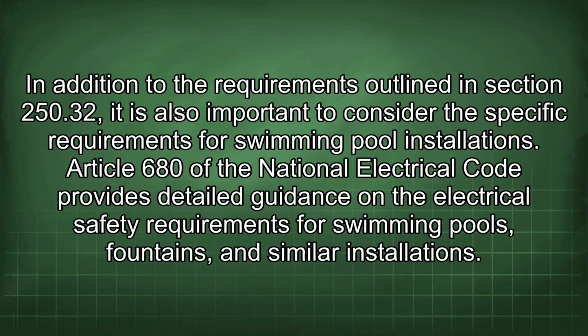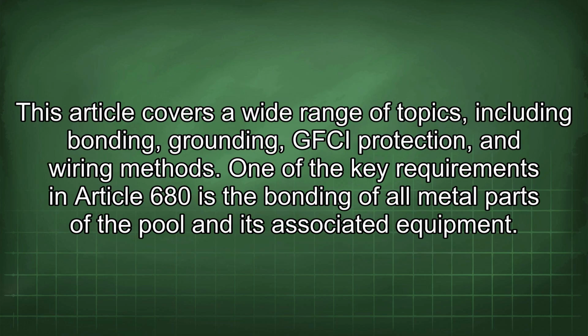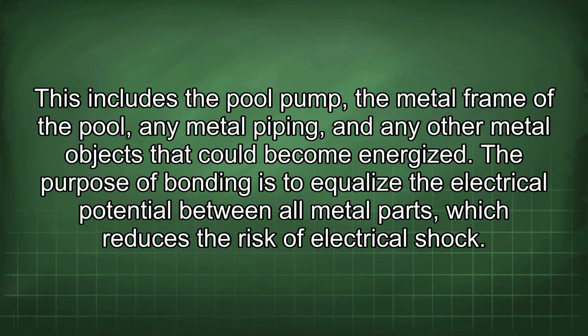In addition to the requirements outlined in Section 250.32, it is also important to consider the specific requirements for swimming pool installations. Article 680 of the National Electrical Code provides detailed guidance on the electrical safety requirements for swimming pools, fountains, and similar installations. This article covers a wide range of topics, including bonding, grounding, GFCI protection, and wiring methods. One of the key requirements in Article 680 is the bonding of all metal parts of the pool and its associated equipment. This includes the pool pump, the metal frame of the pool, any metal piping, and any other metal objects that could become energized.